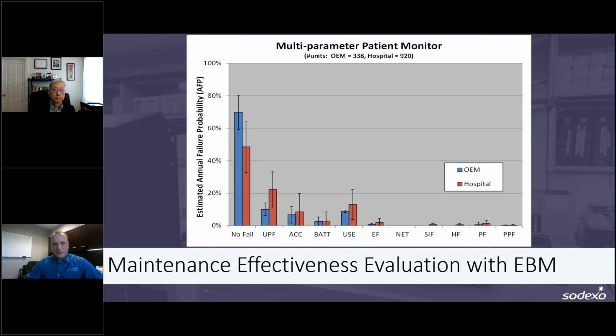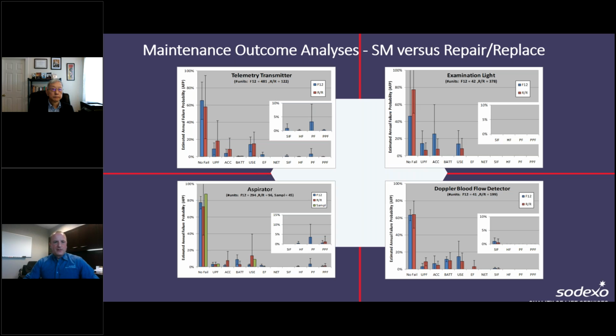Again, the OEM is what I would consider the gold standard. So that being a level playing field, it should be evenly applied across the board. This allows you to look and see how well your maintenance program compares to an OEM style maintenance program. If you look at the average from one group to another, the groups are within standard deviation from each other. So with these overlaps, it's basically meaning that they're all within the standard deviation, so they all are appropriate for use.